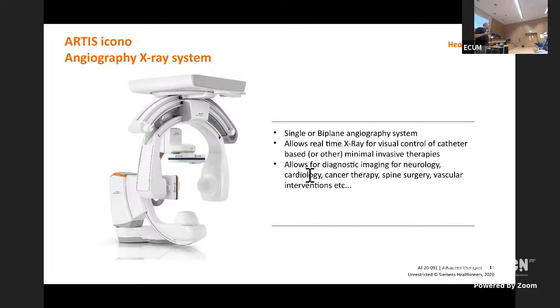We have a lot of performance requirements. We need high image quality with low dose, which are two things that normally are anti-correlated. The higher the dose, the better the image gets, but we don't want a lot of dose for the physicians and the patient. And you need real time, because when you push a catheter in the brain, you need an accuracy of half a millimeter or less. You don't want to have a lag of more than 500 milliseconds or so when you're pushing it by hand. So there are a lot of technical challenges to get this system working.